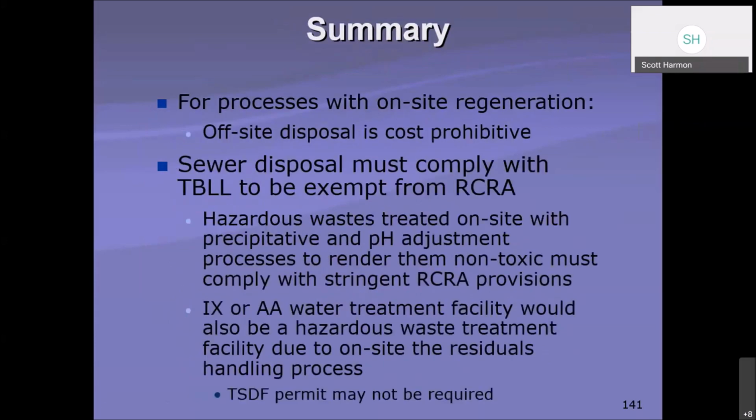The process of on-site regeneration with off-site disposal is cost prohibitive. Sewer disposal must comply with TBLL to be exempt from the RCRA. So again, you have to have an understanding of what the waste system will accept, whether they're going to accept the hazardous waste or not, or whether you're below the hazardous waste levels. Hazardous waste treated on site with precipitative and pH adjustment processes to render them non-toxic must comply with the stringent RCRA provisions. So if that's something you're doing on site, again, you'll have a number of provisions you have to meet for that treatment as well.